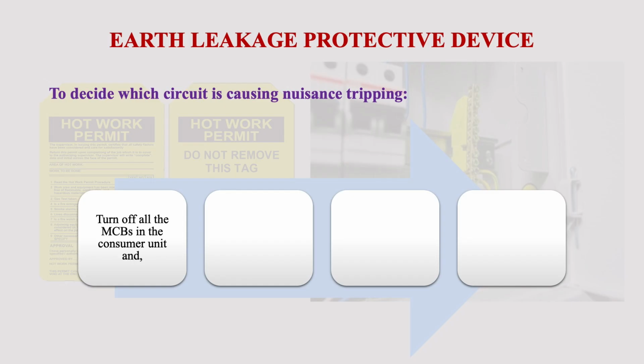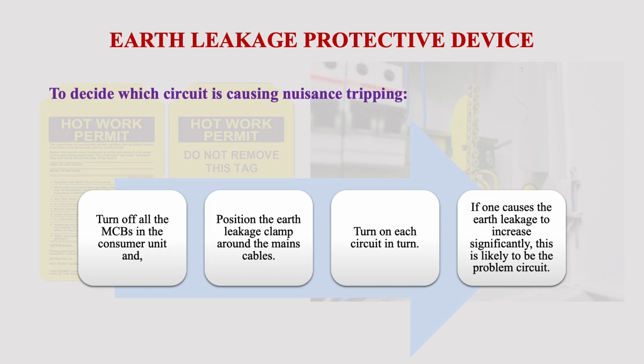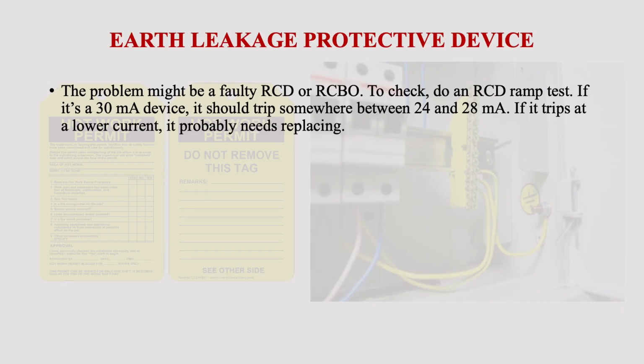In that way, we can determine which circuit is causing nuisance tripping. Turn off all the MCBs in the consumer unit and position the earth leakage clamp around the main cables. Turn on each circuit in turn. If one causes the earth leakage to increase significantly, this is likely to be the problem circuit. Here, don't forget, the problem might be a faulty RCD or RCBO itself. To check, do an RCD ramp test.